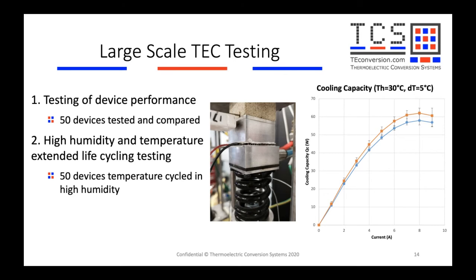So that we could cycle many at the same rate, at the same temperature, and discover any differences. From the graph on the right hand side, you can see the orange curve was the original device they had specified, and the blue curve was the new device they wished to use. The error bars denote that although there's a slight drop in performance, the number of devices we tested meant you could have a similar cooling capacity, although slightly reduced compared to what they originally had.